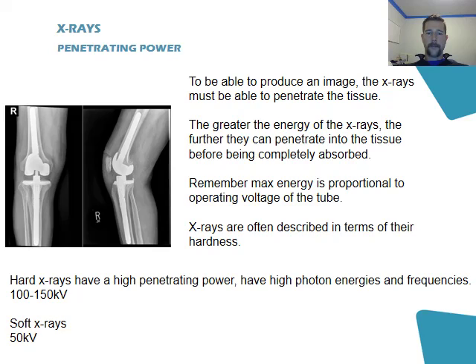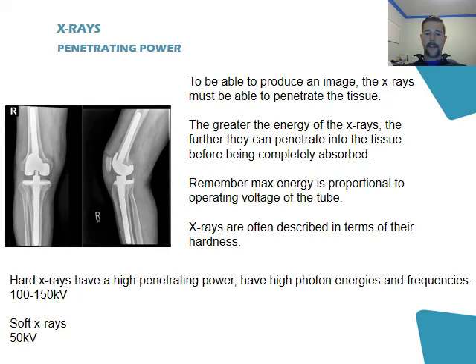The second factor affecting the image produced is the penetrating power. To be able to produce an image, x-rays must penetrate the tissue, and the greater the energy the x-rays have, the further into the tissue they get before they're absorbed. X-rays are often described in terms of their hardness. A hard x-ray has a high penetrating power and goes further into the tissue before it's absorbed, and the penetrating power is in the order of 100 to 150 kilovolts.